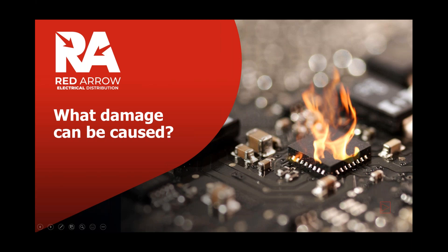What sort of damage can be caused? Transient over-voltages significantly damage and degrade electronic systems. Outright damage to sensitive electronic systems such as computers occurs when transient over-voltages exceed the withstand voltage of the equipment. Equipment damage leads to unexpected failures, expensive downtime, or risk of fire, and in some instances electric shock due to flashover if insulation breaks down. Degradation of systems begins at much lower over-voltage levels and can cause data loss or intermittent outages on electronic components running lighting. Where continuous operation is critical — hospitals, banking, public services — suitable surge protection devices should be fitted.